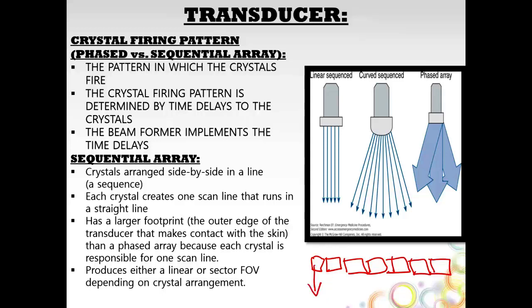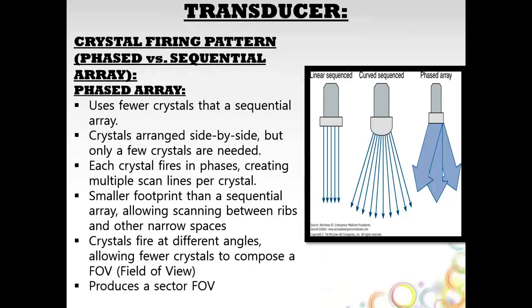Each crystal is going to create pulses that come out of this crystal, and all these pulses, as they come back to the transducer, are going to end up creating one scan line. These sequential arrays, the crystals fire one at a time, down the row or curve or whatever pattern they're in. And you're going to have a large footprint with these since they're not firing in a phase, but they're firing singly. And that's because each crystal is responsible for one scan line of the image. And these are going to provide either a linear or a sector field of view, just depending on how those crystals are arranged.